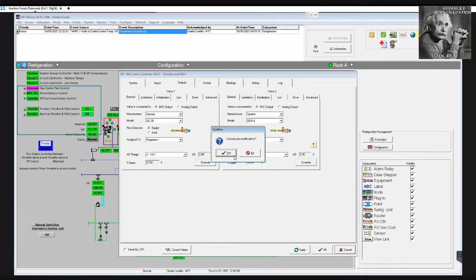Just to close this picture, so what we have going here is, if the CO2 has gone past the critical point, and I've got a supercritical undefined fluid, then I have to make sure I can have enough of a pressure drop here so that I can urge that CO2 to come back to a liquid state.